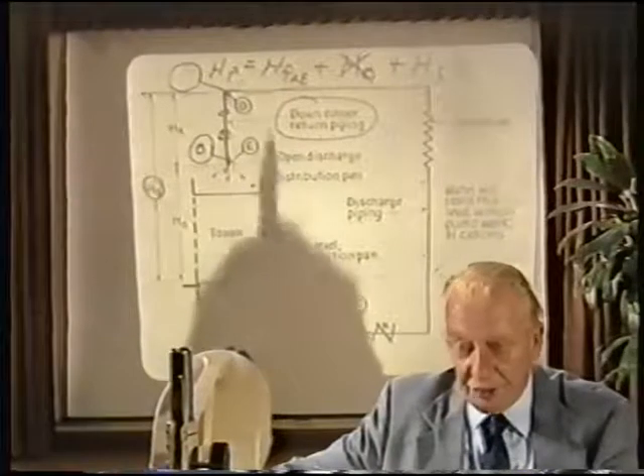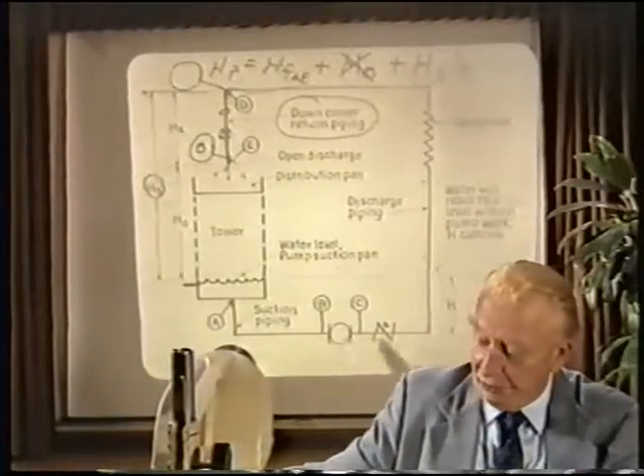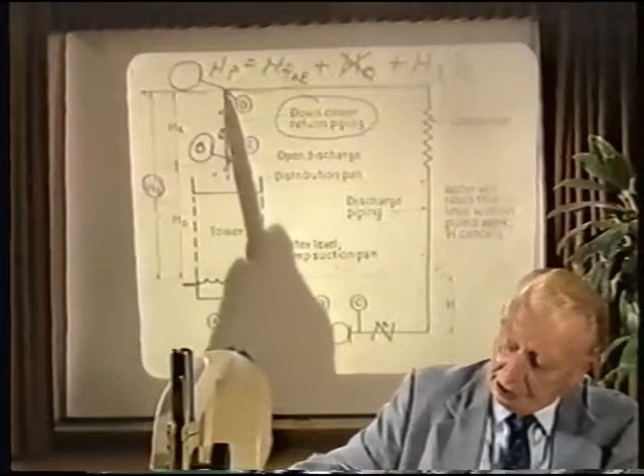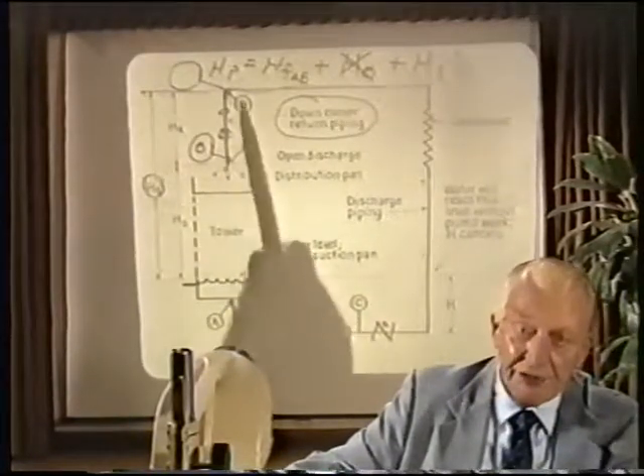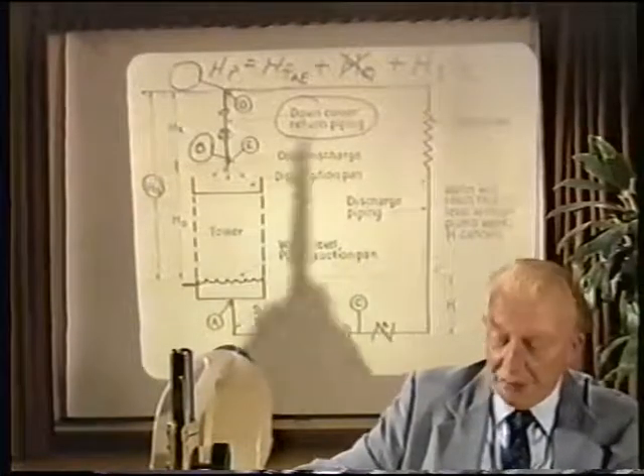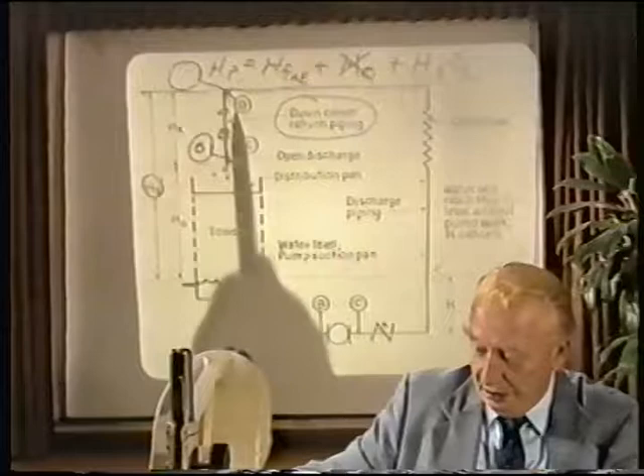And it's amazing to watch a system such as this when the pump starts. With that pump startup, until such a time as the siphon draw occurs, we have a very low flow rate in the condenser piping system. There is a brief discussion of this problem in our design manual entitled Cooling Tower Piping and Pumping Practice, and it covers the situation in more detail than is outlined here. But conceptually again, when the cooling tower piping system is designed, consideration must be given to that downcomer return piping.